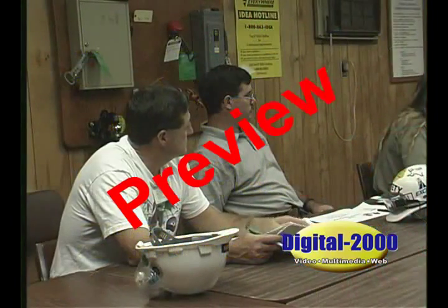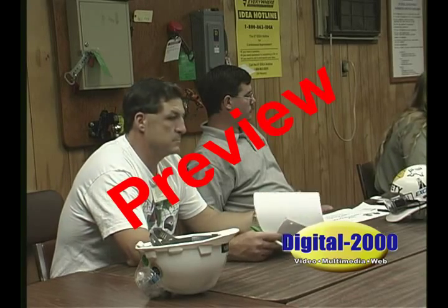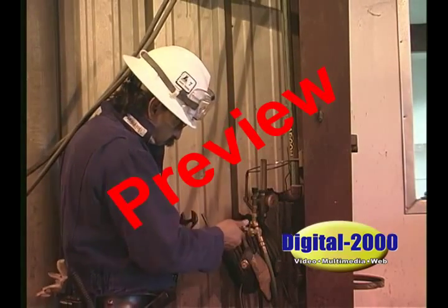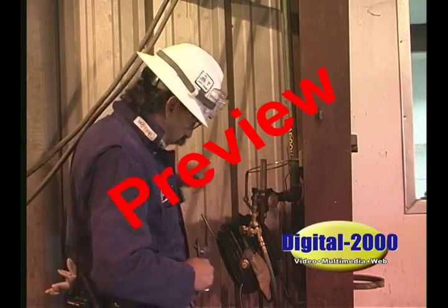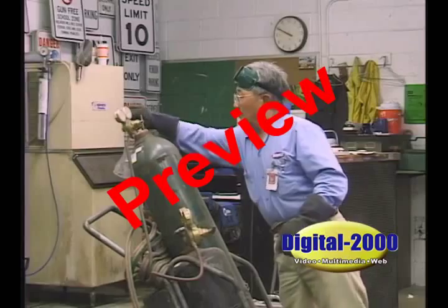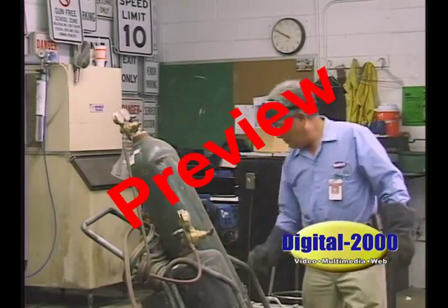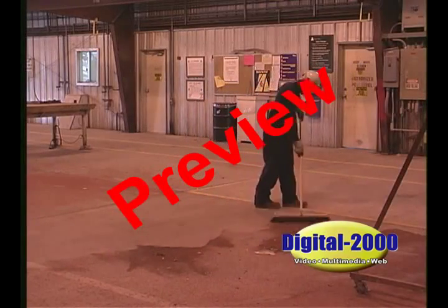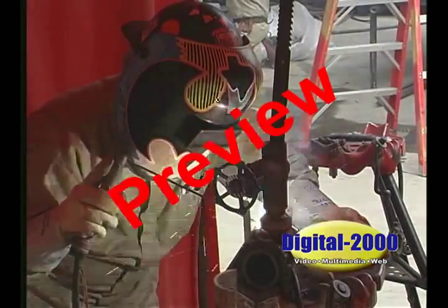The fire marshal, safety engineer, maintenance manager, or other person designated to issue hot work permits has the responsibility to verify that all necessary precautions have been taken at the work site. Some of the precautions include making sure the sprinkler systems are in service and all cutting and welding equipment is in good repair. Keep in mind, the work area that will be used should be cleared of any debris for 35 feet. That's the distance that welding sparks or slag can be thrown.